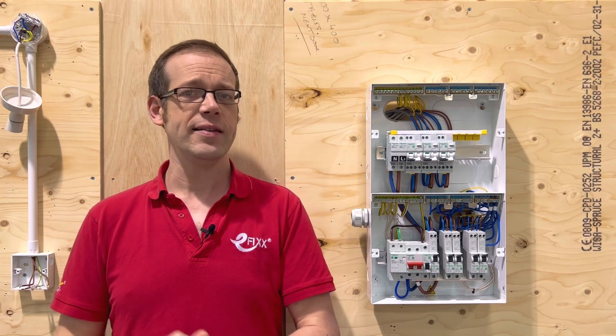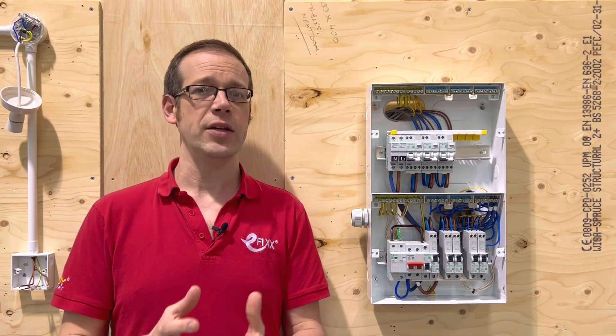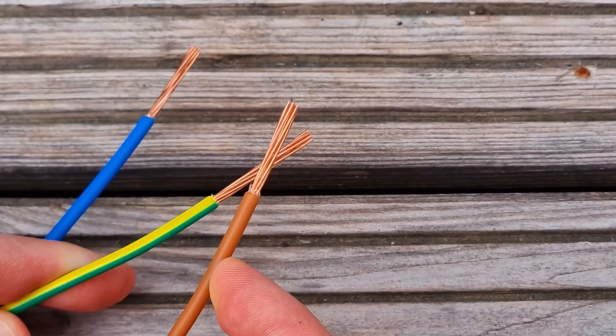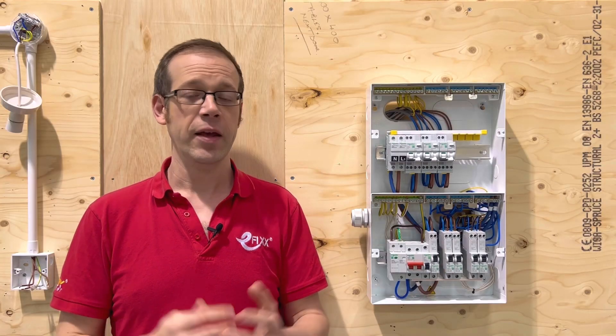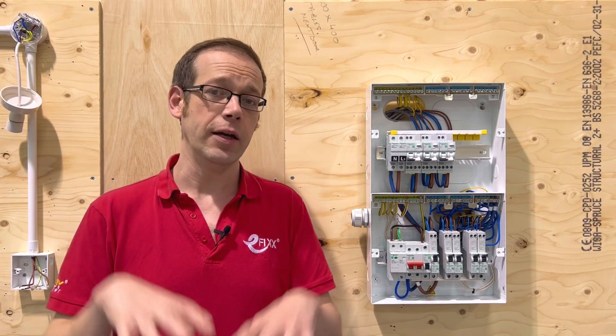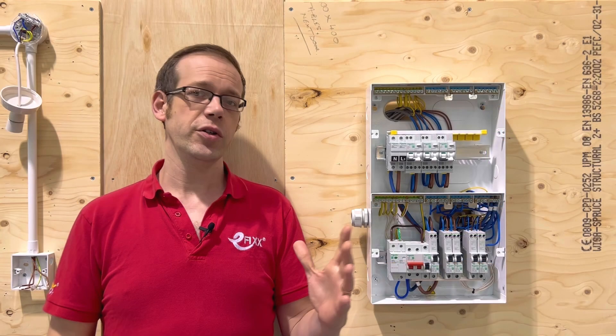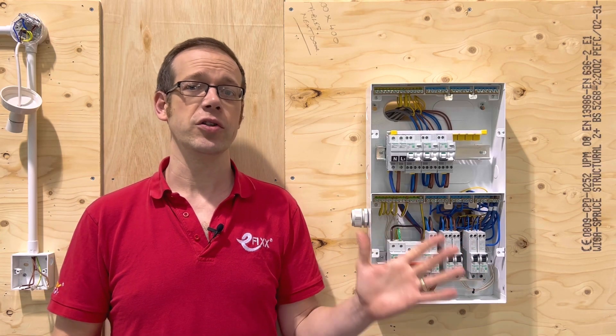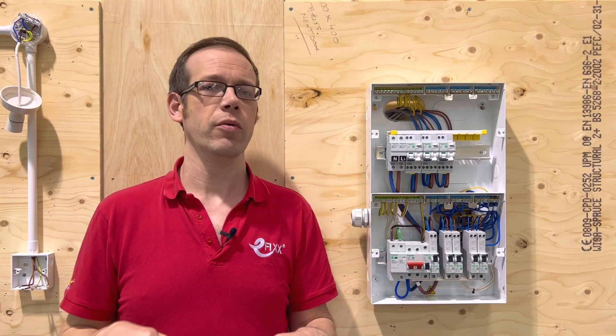But what is this additional protection that it offers? Well when we were discussing MCBs we mentioned what happens when a line conductor comes into contact with a CPC or an earthing conductor. The resistance of the circuit becomes very low, current flow therefore becomes very high and the MCB disconnects quickly. But does the same thing happen when a person comes into contact with a line conductor? Well when someone touches a line conductor they generally will receive a shock to earth.